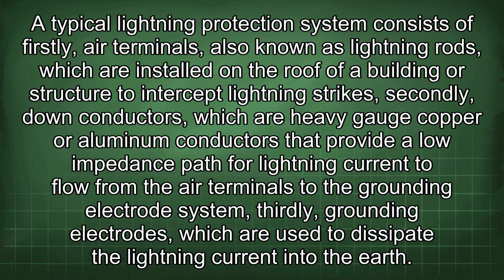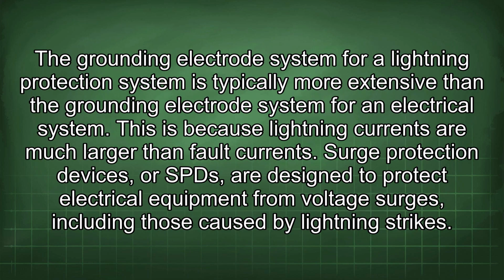Secondly, down conductors, which are heavy-gauge copper or aluminum conductors that provide a low-impedance path for lightning current to flow from the air terminals to the grounding electrode system. Thirdly, grounding electrodes, which are used to dissipate the lightning current into the earth. The grounding electrode system for a lightning protection system is typically more extensive than the grounding electrode system for an electrical system. This is because lightning currents are much larger than fault currents.